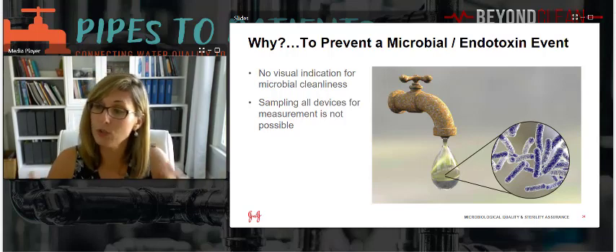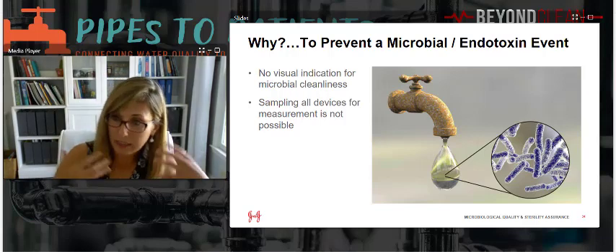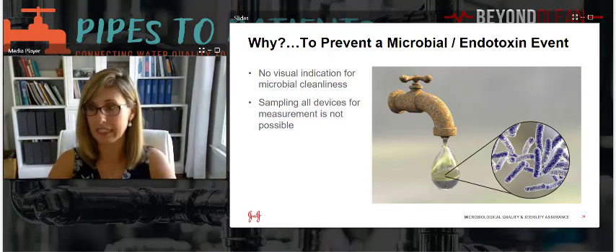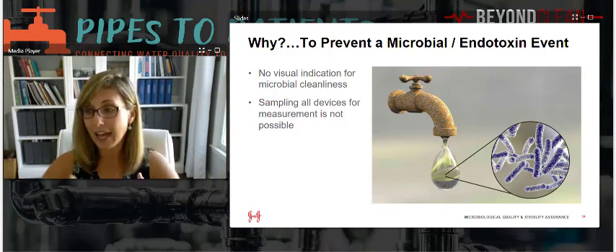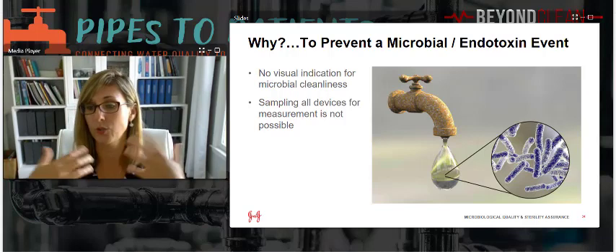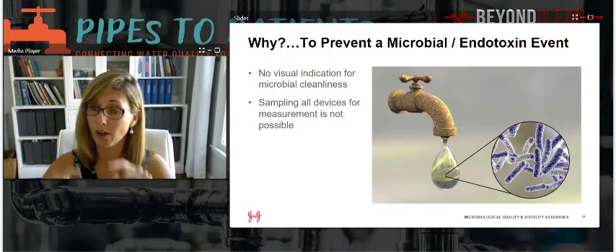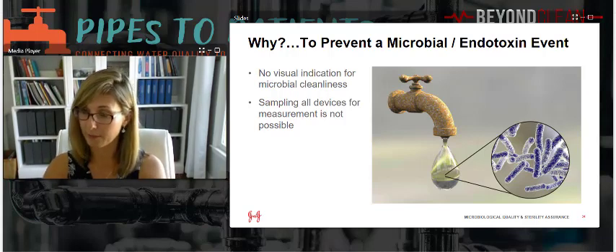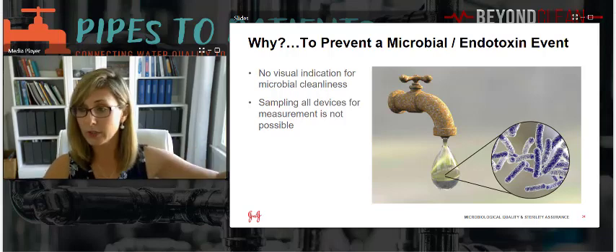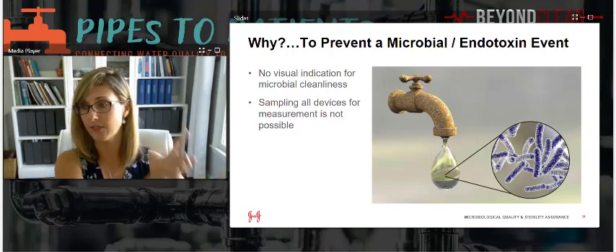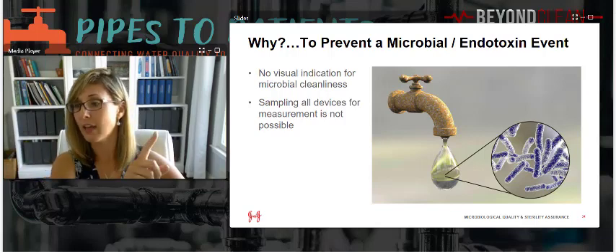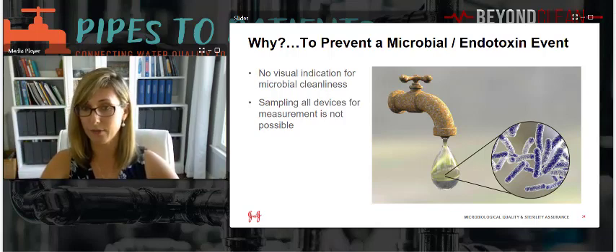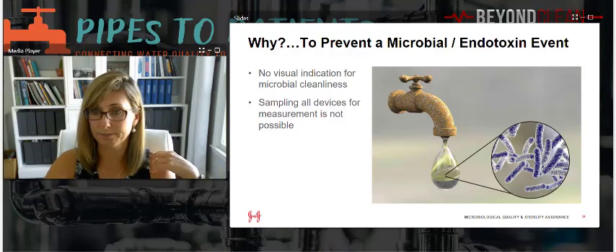So this is why we do point of use monitoring. This is a new requirement in ST108, where you will be sampling at the point of use, at the faucet you use to process devices, to make sure the water there is of the right quality. Just because it comes out of the water treatment facility or system at an okay quality doesn't mean that as it follows through the piping, it isn't getting more and more problematic before it gets to you in sterile processing.